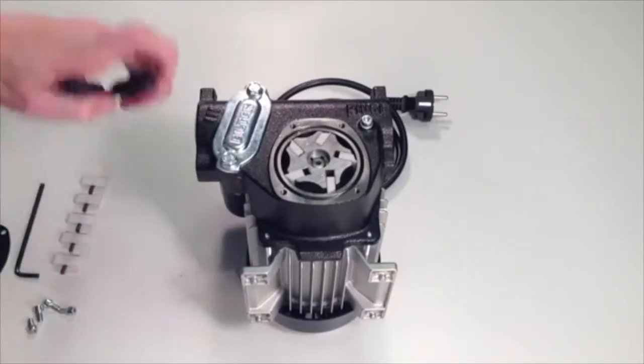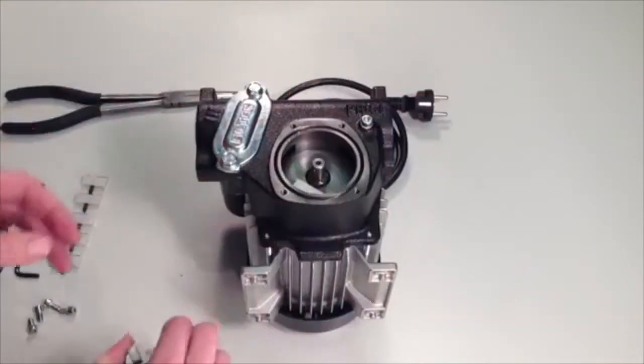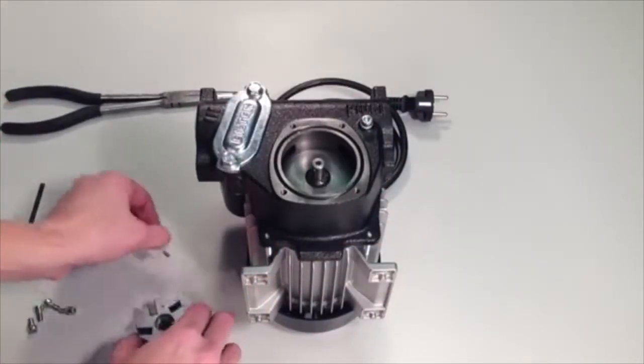Now use the long nose pliers to remove the rotor and vanes from the shaft of the pump. The vanes are spring loaded so they will eject from the rotor if you do not hold them in place. Remove the 5 vanes from the rotor and place the rotor back in the pump.